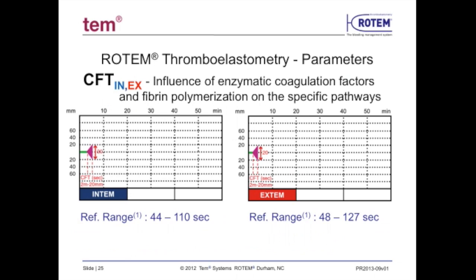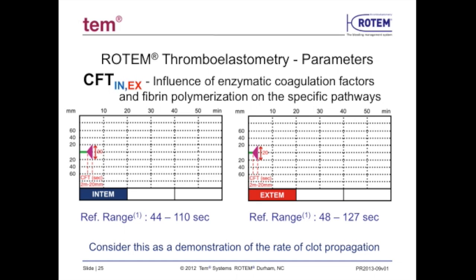The clot formation time is developed by measuring the time it takes from the end of CT formation at 2 mm to reach an amplitude measurement of 20 mm of clot strength. Consider this as a demonstration of the rate of clot propagation.